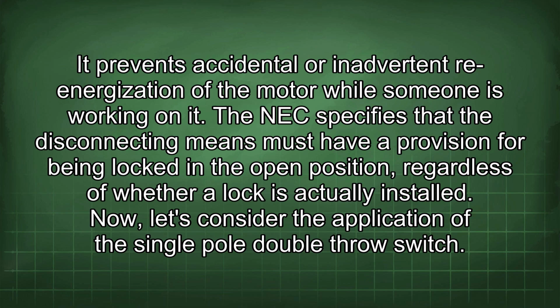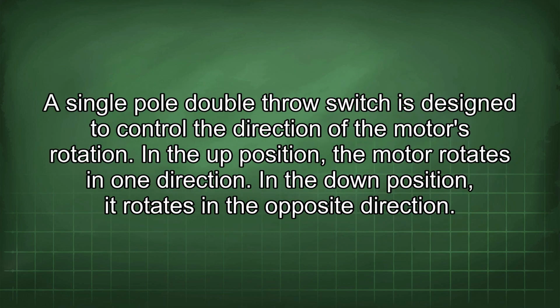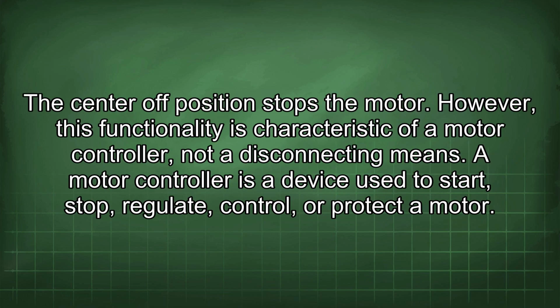Now let's consider the application of the single-pole double-throw switch. A single-pole double-throw switch is designed to control the direction of the motor's rotation. In the up position, the motor rotates in one direction. In the down position, it rotates in the opposite direction. The center-off position stops the motor. However, this functionality is characteristic of a motor controller, not a disconnecting means.